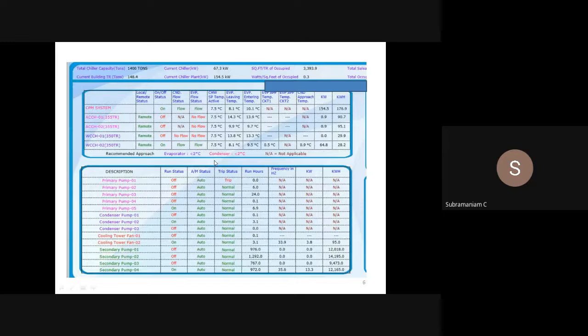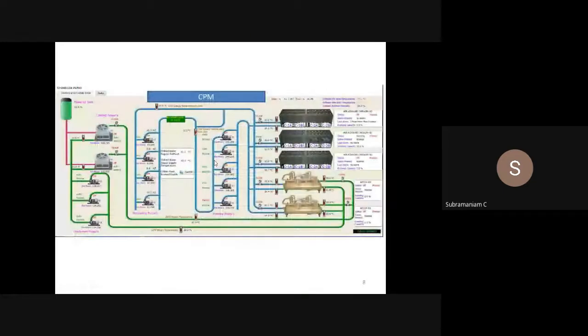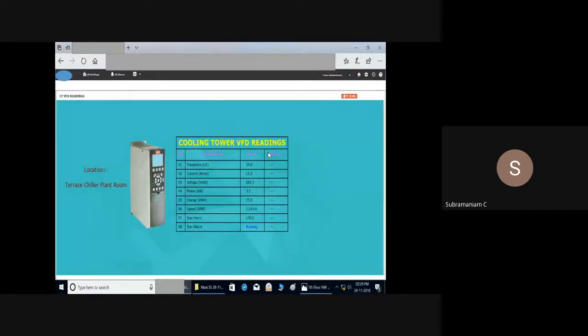Look, one screen can give you multiple values there. And this is the graphic screen which we can create, which is very important for the operator. What all parameters, what all equipment are there, whether it is working. For example, I have a motorized valve at the evaporator outlet, chilled water evaporator outlet. If I have a primary, secondary system, sometimes the actuator may be faulty. It will be in open position, it will tell me close. It may be in closed position, it will tell me open. So we have to check all this physically and see whether in graphics it is correct or wrong for all our operations purpose. Then cooling tower VFD.